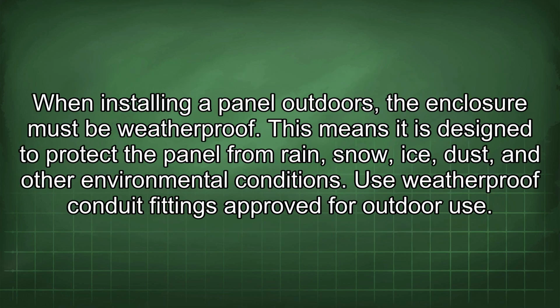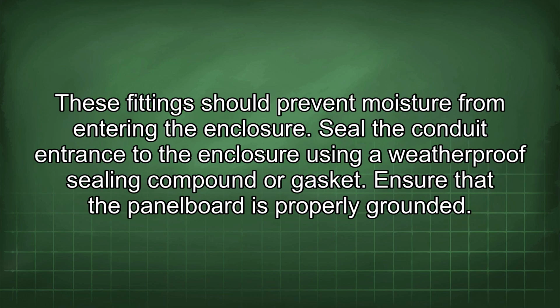When installing a panel outdoors, the enclosure must be weatherproof. This means it is designed to protect the panel from rain, snow, ice, dust, and other environmental conditions. Use weatherproof conduit fittings approved for outdoor use. These fittings should prevent moisture from entering the enclosure. Seal the conduit entrance to the enclosure using a weatherproof sealing compound or gasket.